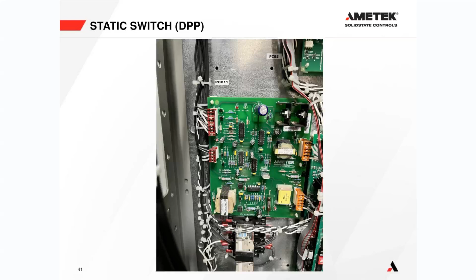And then on a single phase system, PCB 11 is our static switch gate drive board. There are actually two LEDs that tell you if an SCR has failed, and an inverter to load LED there as well. Okay, that's the interface between the inverter static switch control board and the static switches themselves. Remember, there's always isolation between the control board and the SCRs. So this is our inverter gate drive board.